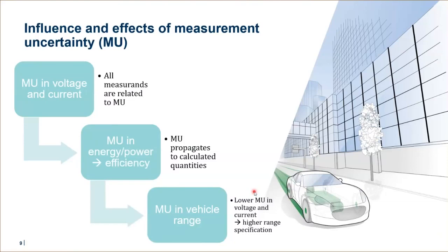And in addition to that, all measurement equipment, independent from the manufacturer, each sensor, each power meter, contains a lot of different components, and all have manufacturing tolerances. And independent from the level of quality, it is impossible to build a really absolutely perfect system. And for those two reasons, each measured quantity contains measurement uncertainty. And if we now think again about our electric drivetrain, we measure voltage and current. Both of the measurands contain measurement uncertainty. And then we calculate energy, power, or efficiency from these measured quantities. And of course, the measurement uncertainty of the measured data propagates to the calculated data.